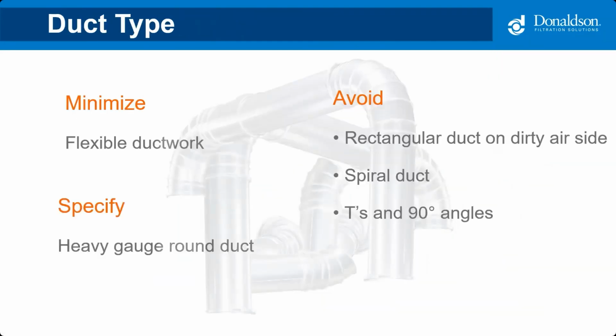Just a few quick pieces of advice when it comes to duct type. Rectangular duct is commonly used in HVAC applications where you're moving air only. We don't want to use this in industrial applications because dust settles out in the corners. It's okay for the clean air side. When specifying industrial duct systems, make sure to call out round, heavy-duty industrial ductwork.